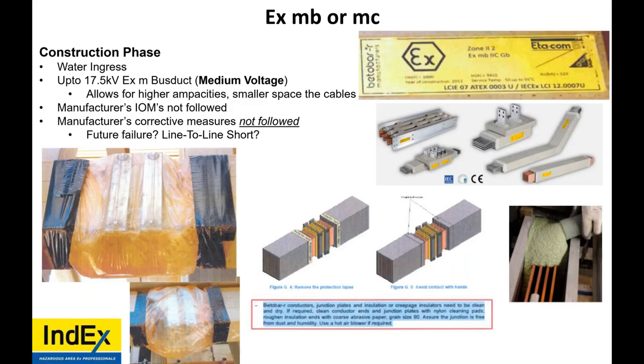Now, its terminations on the ends must go into another EX type of protection, say an EXE enclosure. So preservation was not done. The correct methods of dealing with it were not followed. And I would not be surprised if water seeped into the encapsulating concrete or whatever type of compound it was. We're dealing with tight tolerances on creepage and clearance distances on medium voltage. It's a good product, but it was not preserved or installed correctly.